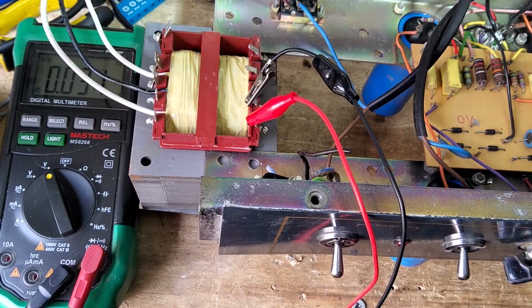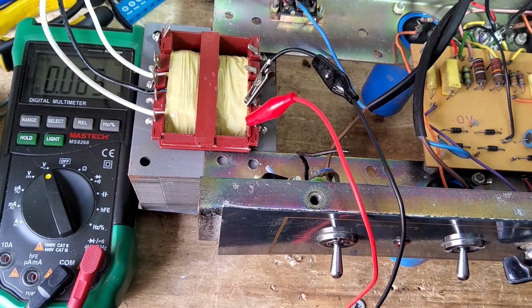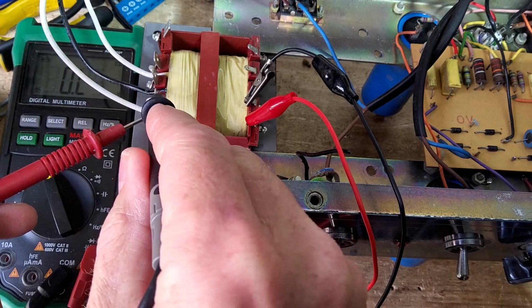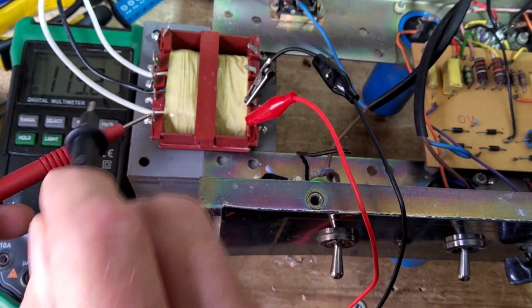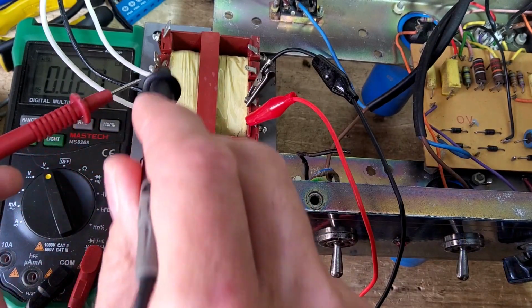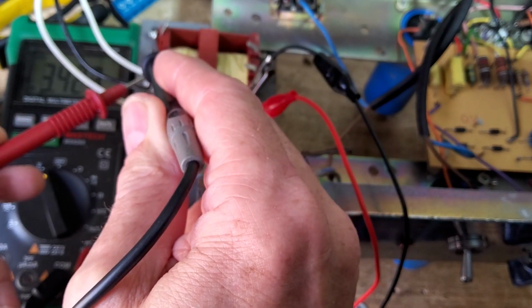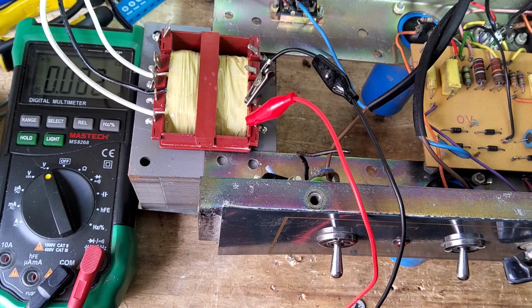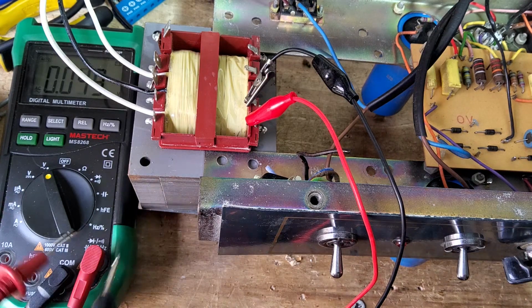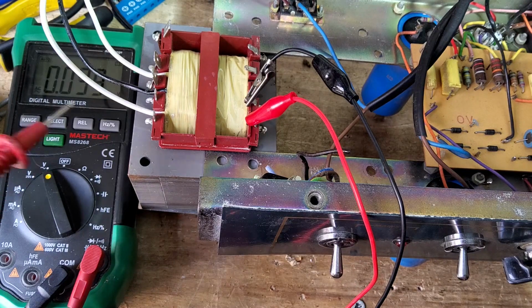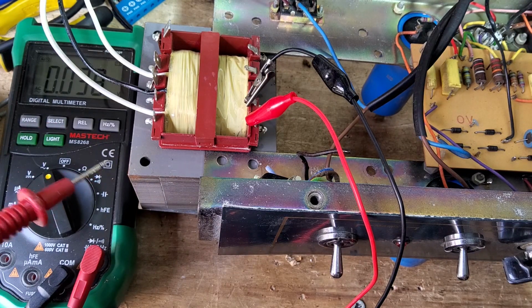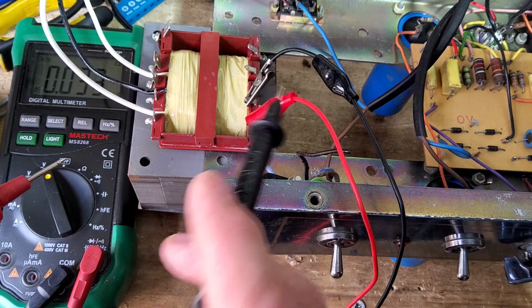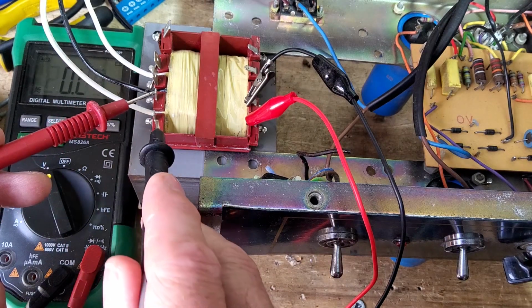Now we're at, I've got 50 volts on the variac. We're having to be careful now what we're doing. And we've got 175 on there. What we've got on this filament, what we think is the filament voltage, 3.4 at 50 volts. Well, if that's a filament voltage and I've got 3.4 volts at 50 volts, then that's telling me that could be a 110 volt tapping.